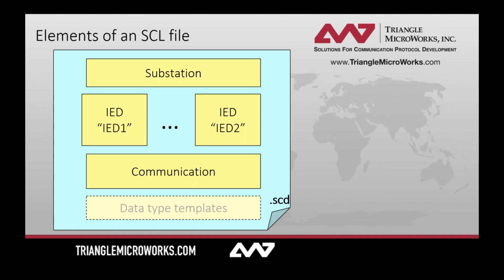DTM is currently parsing through the SCD file exported by Helix STS. It'll parse through 3 different sections of the SCD file. The substation section is the functional part, including the topology information for the one-line diagram. DTM will be reading this in order to figure out how the electrical equipment should behave together.